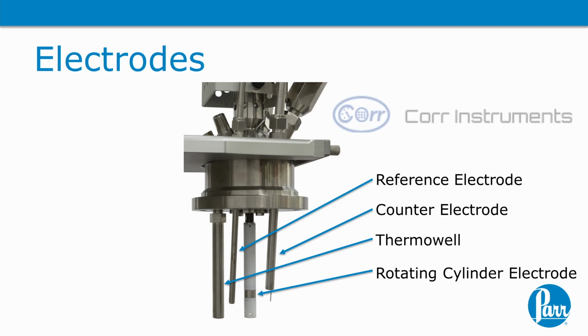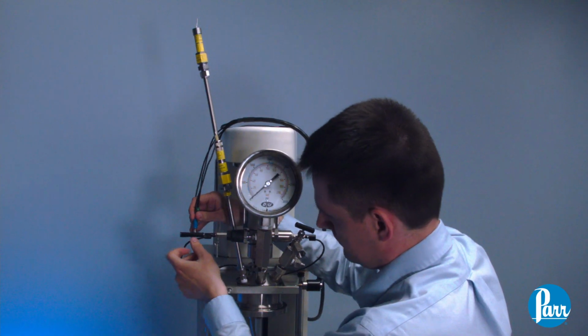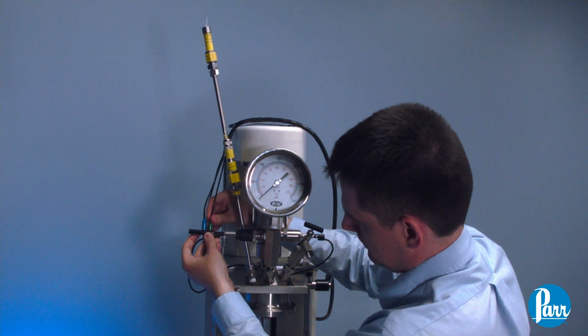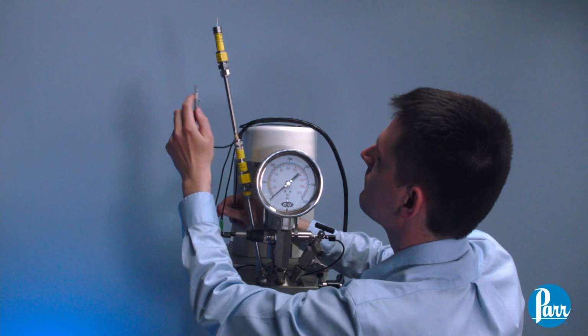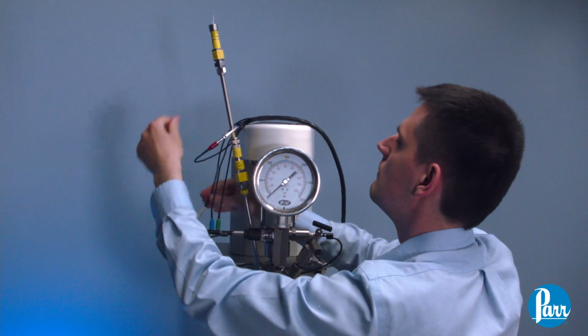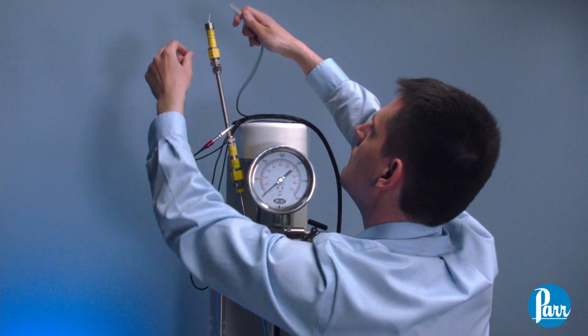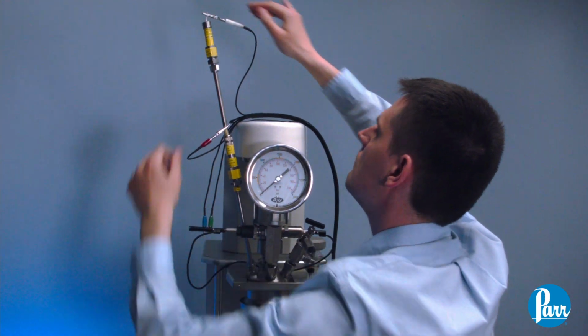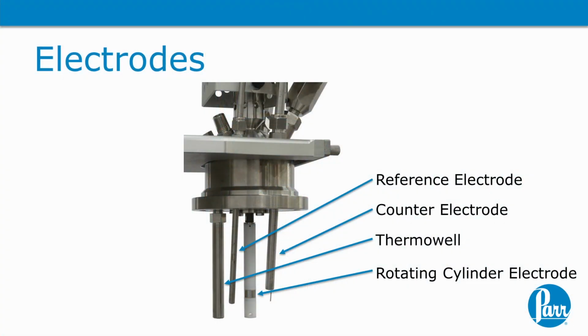The reference electrode is a silver chloride high pressure, high temperature Corr Instruments probe, which is refillable and can be used up to the 200 degrees C temperature conditions of the system. It can be supplied for the pressure rating of the system also. The counter electrode is a 1 mm OD platinum Corr Instruments probe. They are mounted through a compound angled port into the head of the pressure cell.